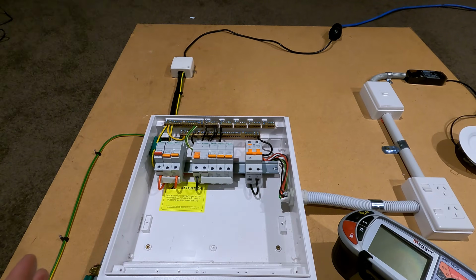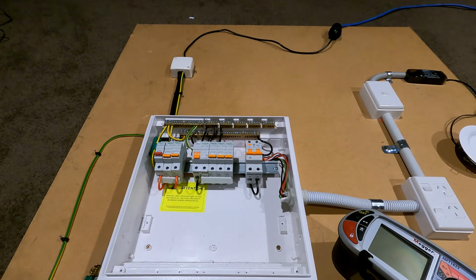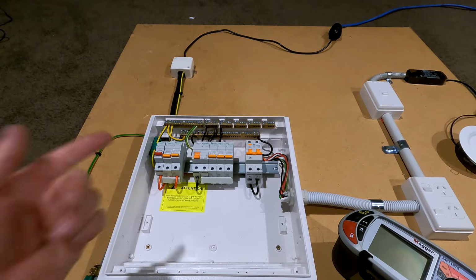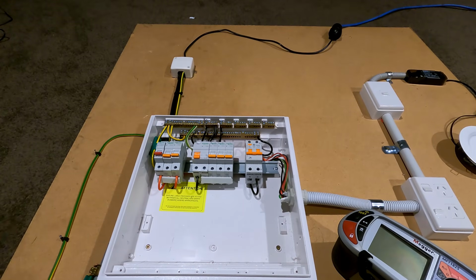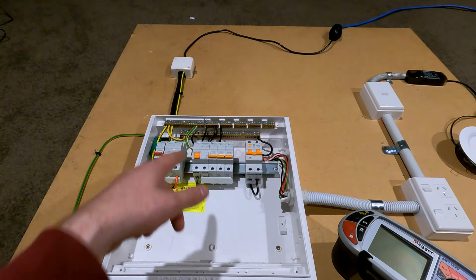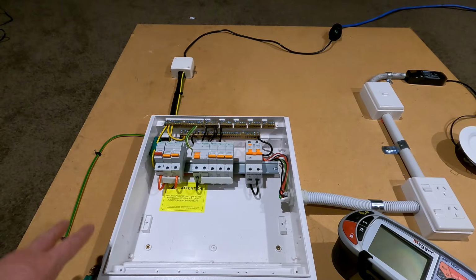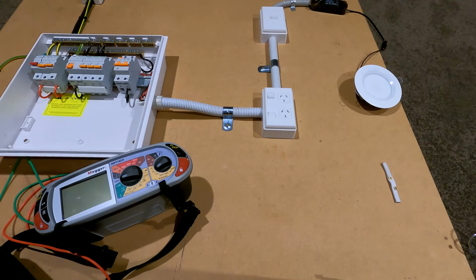is we could put a remote earth outside somewhere, run our trailing lead, fly lead out to it, and back to the board here, and we'd test between our remote earth and our known 230 volt source and ensure there's 230 volts between them, and then we'd test between our remote earth and our earth neutral bar, which has its own fixed main earth, and we'd ensure there's 0 volts between them. This test simply verifies the polarity is correct on the line side of the meter, so the street connection side of the installation is correct.